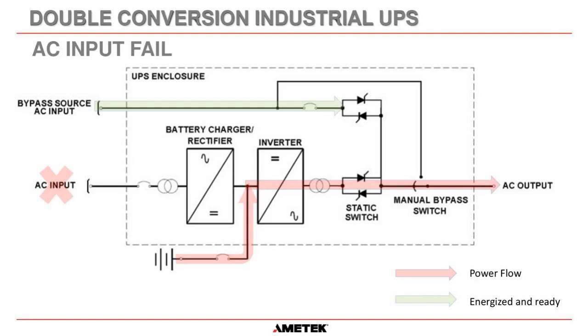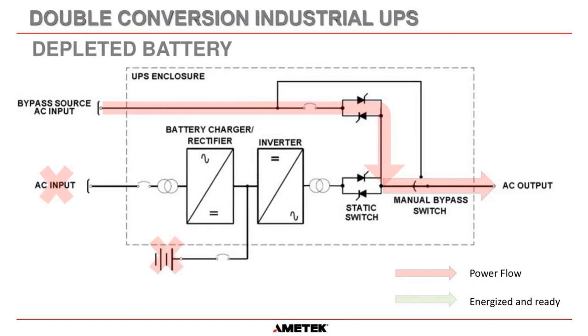Now, the system is going to run on battery either until the power comes back on again or until the batteries get depleted. And when the batteries get depleted, the UPS senses that we're getting down to a voltage that could damage the batteries. So the disconnect between the battery and the UPS is tripped, and that means the DC going to the inverter is lost, and the system will sense that. As soon as it senses that, it sends a signal to the bypass static switch, not the manual bypass switch, the static switch. And that transfers the power to our bypass source, as you can see in that red line, through the manual bypass switch out to the critical loads.